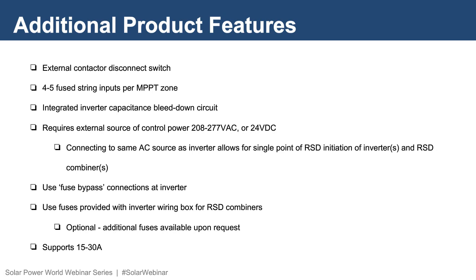These boxes use a remote control power source to signal the rapid shutdown. This source can be simply supplied as the same source that supplies the string inverters, allowing a single point of disconnect.